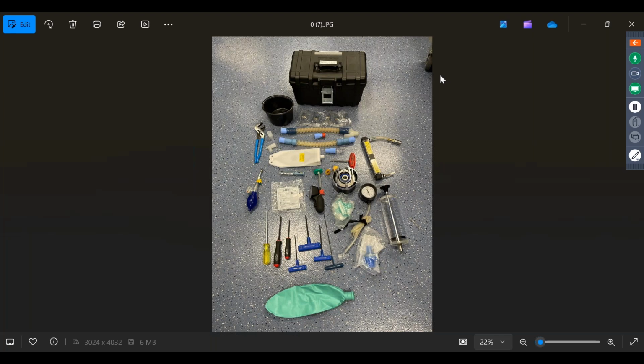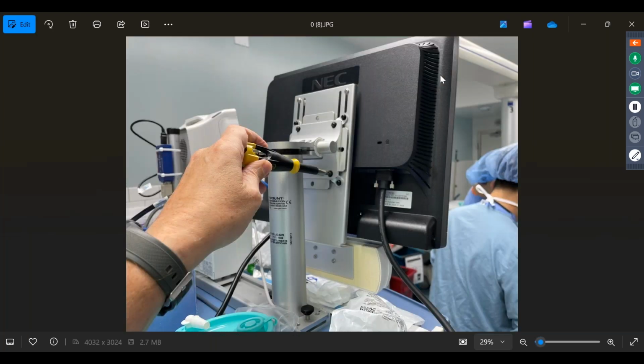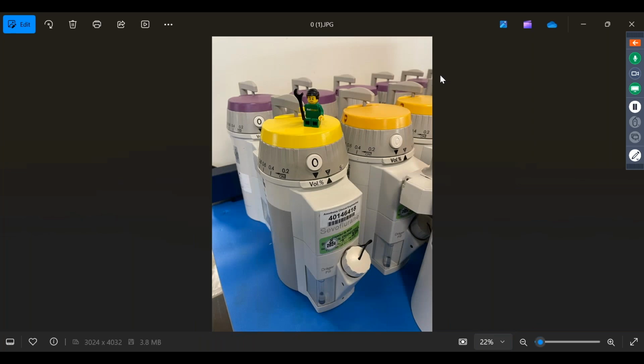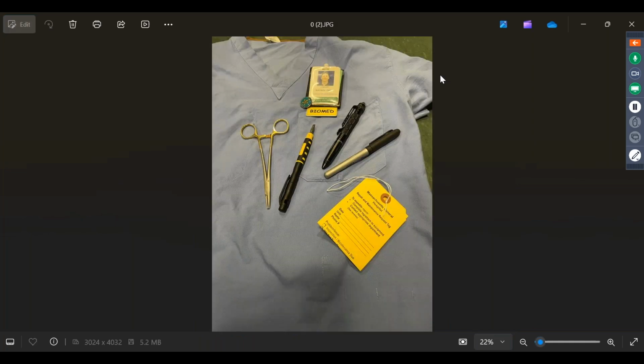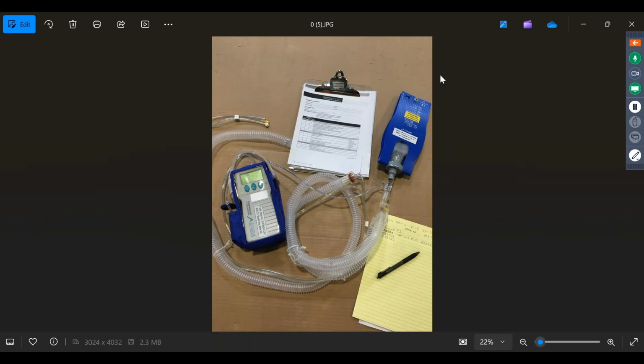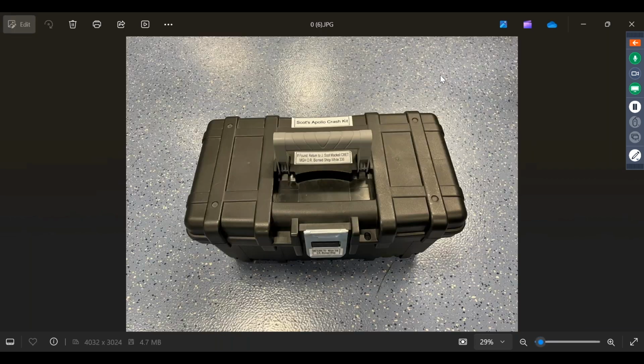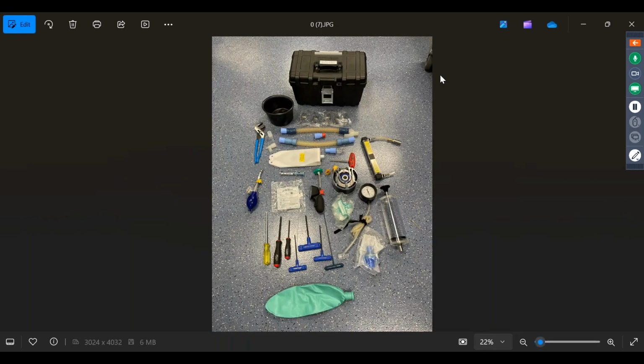This is a gauge that measures. See these things? One of the worst leak problems, they'll hit that with their knee or bang something into it and they'll bust the seam open and you'll have a machine leak. It mimics a patient leak and it's hard. So one of the first things I do if we have a persistent leak like that, I will get out the tester and I'll be able to test it. So that really helps. Airway pressure.